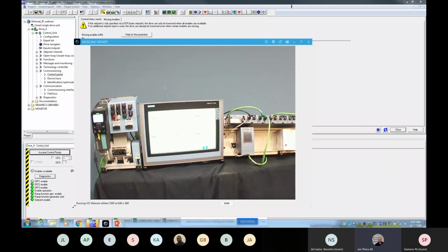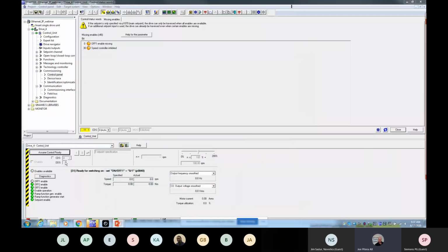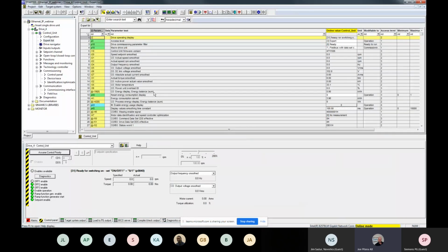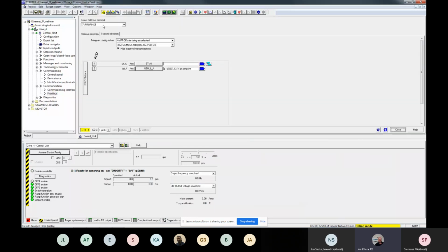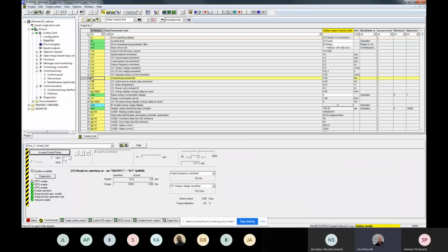Okay, so now we showed that we were able to commission the drive and run it from the Siemens PLC relatively quickly. Our next objective here is going to be selecting the drive to run on EtherNet IP instead. So by going to the expert list here, you can do this through the IOP as well, or we can go to the field bus and change this from Profinet to EtherNet IP, or we can go to the expert list and I'll show you the actual parameter here that needs to be converted. By typing in the parameter quickly, you can go right to the parameter.